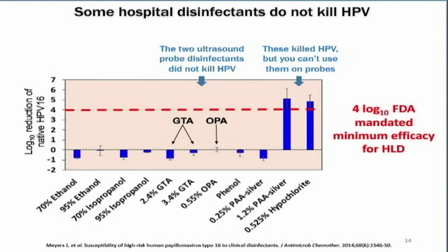So here's a graph of our results. I'll give you the punchline right off: some hospital disinfectants do not kill HPV. On the left, you can see this is a log 10 reduction of native HPV. The dotted line is a 4 log reduction, which is mandated by the FDA as the minimum efficacy for high-level disinfectants. So every point above the 0 line is a 10-fold decrease in infectious HPV. Now, you can see right off here that most of these disinfectants were inadequate, had no efficacy to deactivate or kill HPV virus.